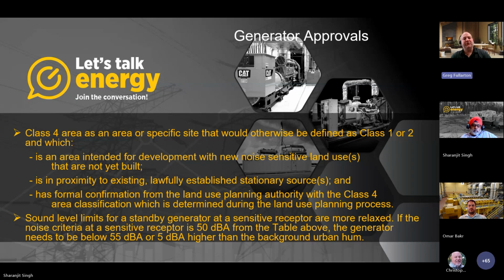Now, sound level limits for a standby generator at a sensitive receptor are more relaxed. When you have a global adjustment 5 megawatt gas-fired generator unit, you're assessing the noise from that as well as the rooftop comfort equipment, any cooling towers, anything else that might be on site - could be truck traffic and everything else. You're going to do a cumulative noise impact with that generator, as that's not deemed a standby generator - that's prime power global adjustment.